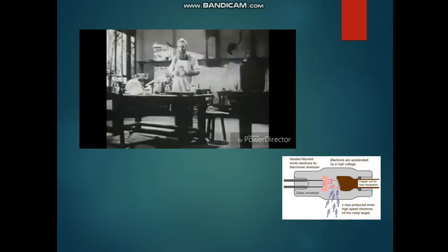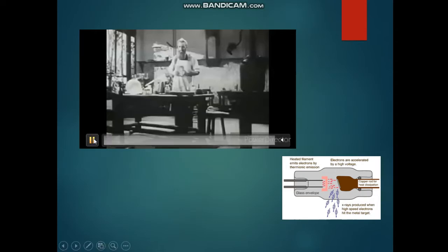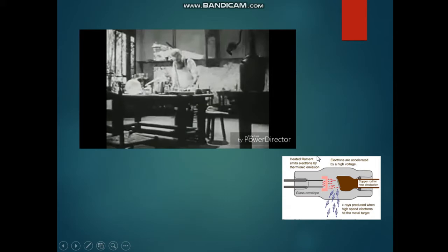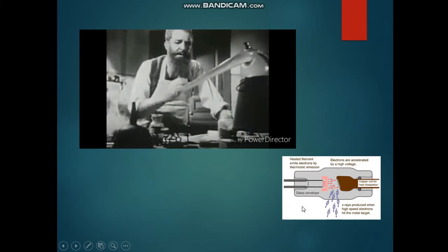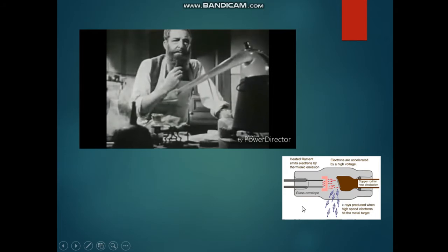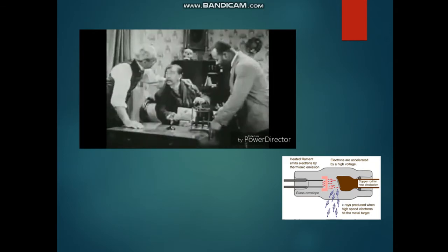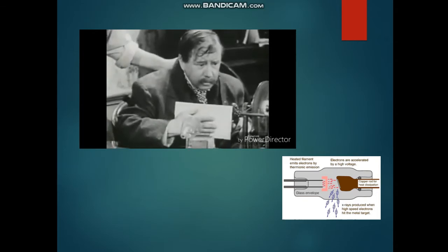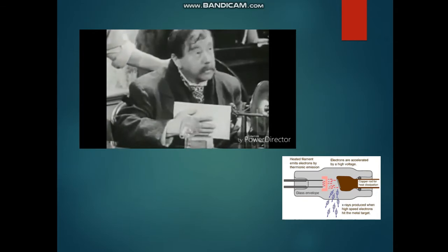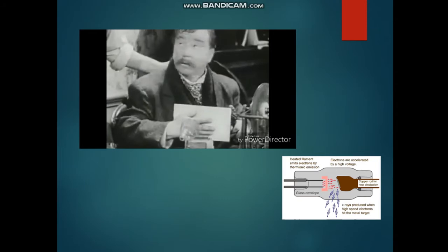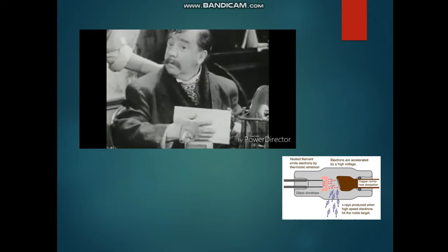In this picture, you can see an X-ray tube. An X-ray tube is the source of X-radiation. X-rays for medical diagnostic procedures are produced in the standard way by accelerating electrons with a high voltage and allowing them to collide with a metal target.